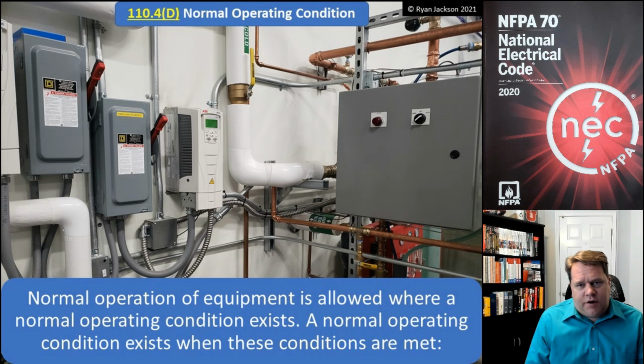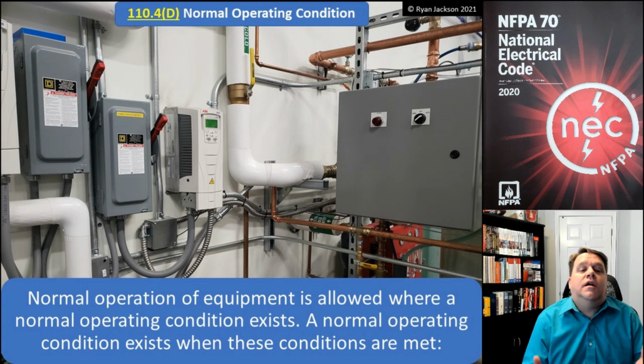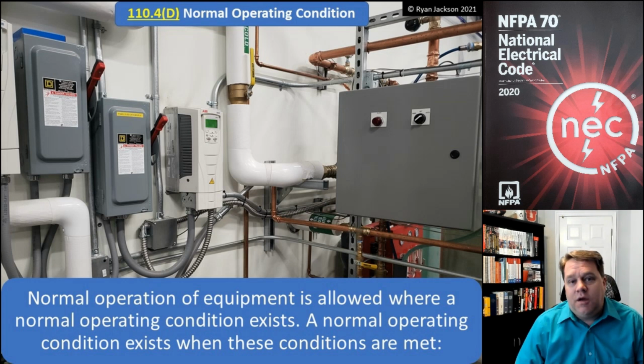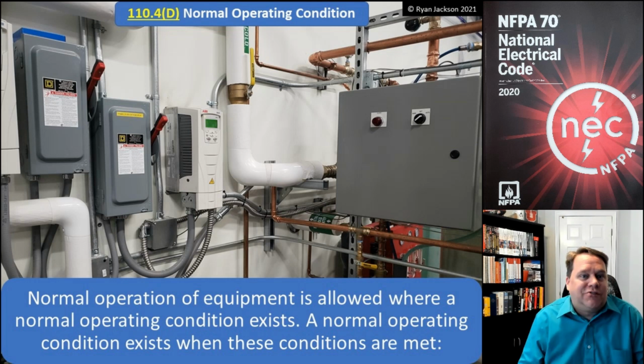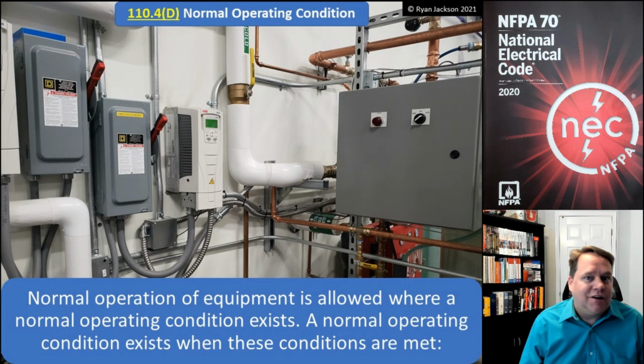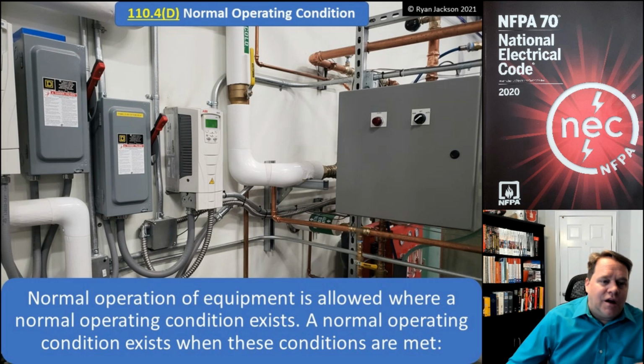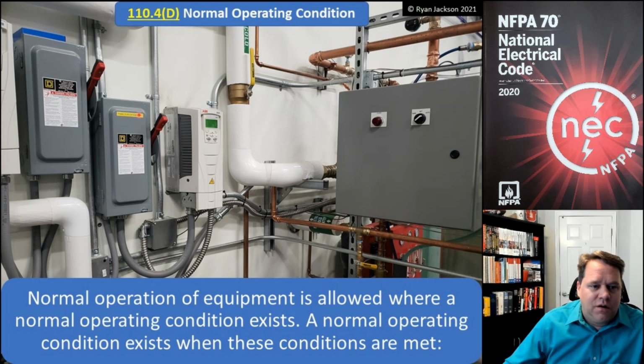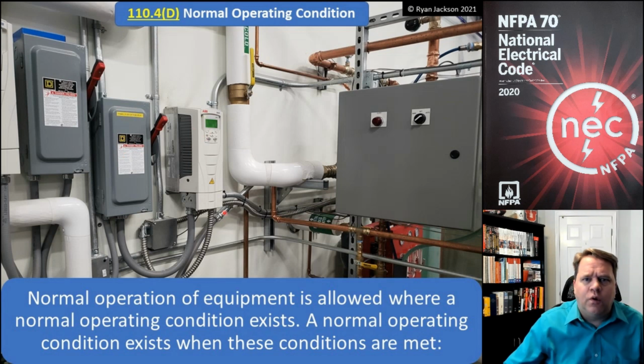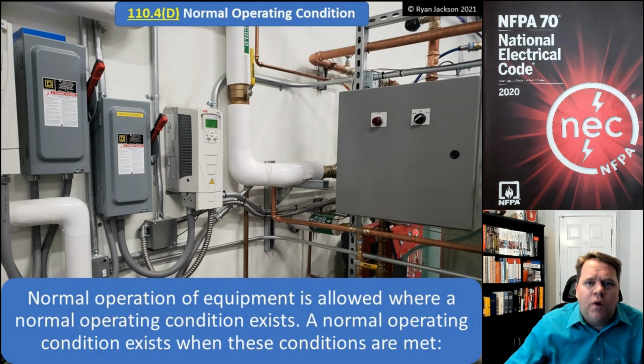This is where people start to get really frustrated. And they say, oh my gosh, 70E, what a joke. You can't even turn on a light switch without wearing PPE. Well, no. That's not true. That would only be spoken by somebody who's never read 70E, because normal operation of equipment is allowed if there is a normal operating condition. So, can I walk up to this disconnect switch here and use the disconnect, turn it off and on? Sure. Yeah, of course. That's what it's for. That's fine. Normal operation of equipment is allowed as long as a normal operating condition exists.